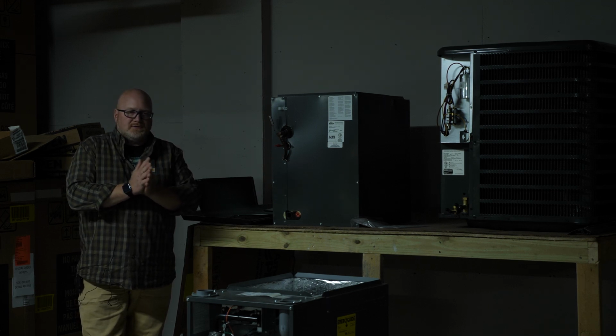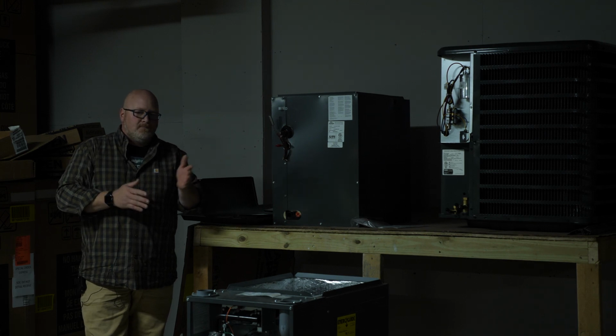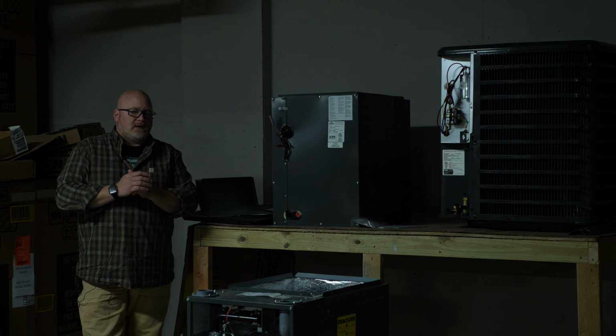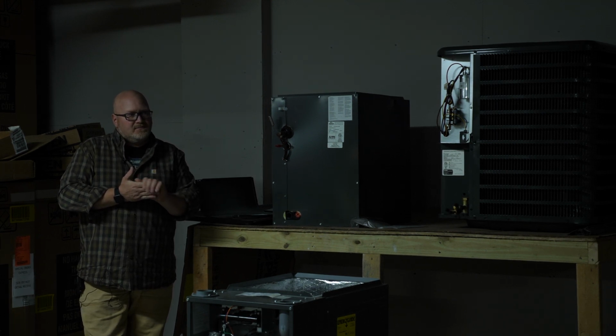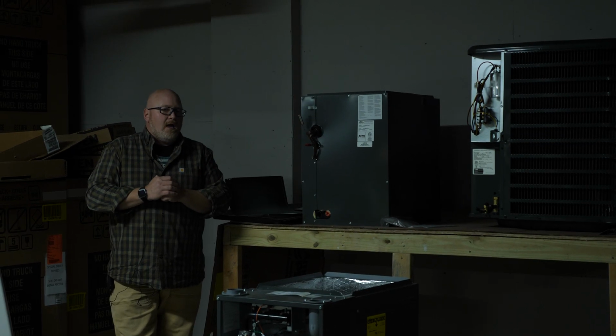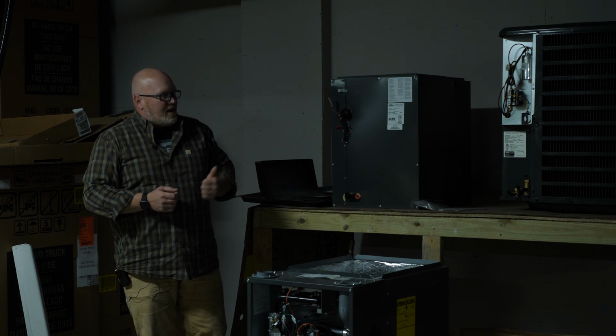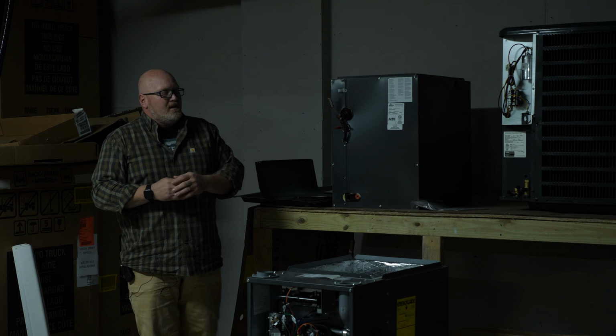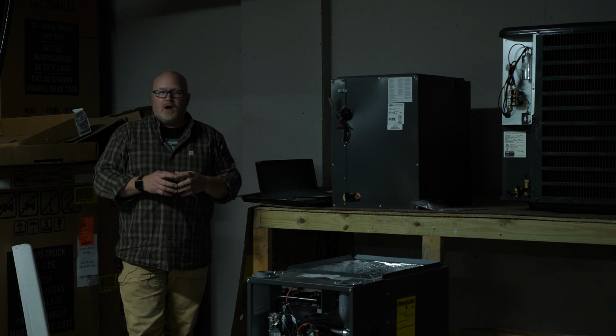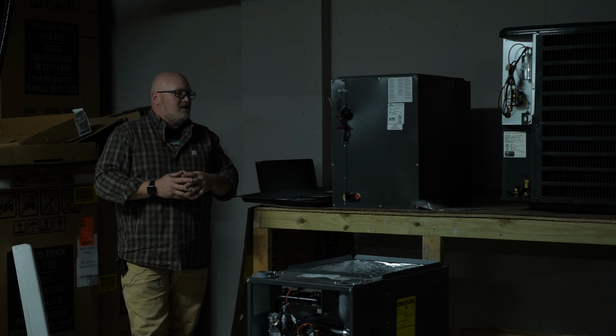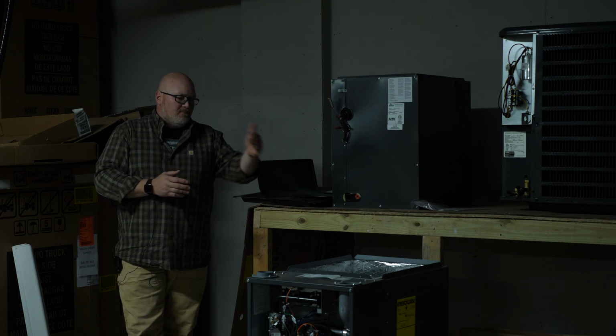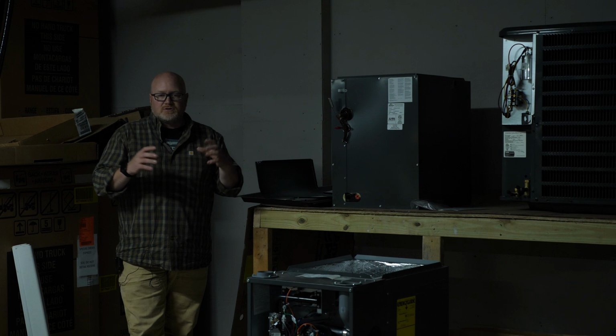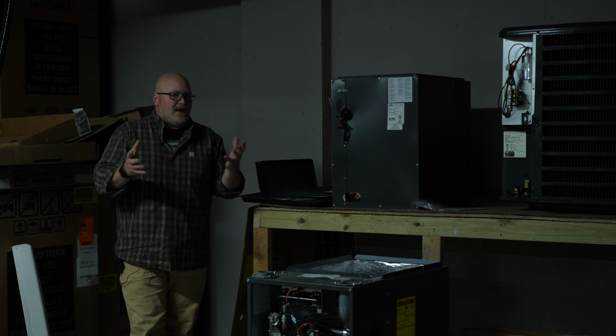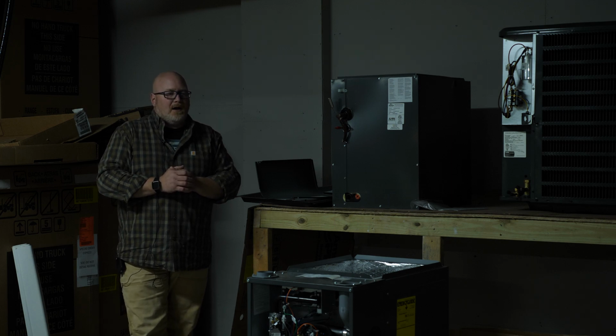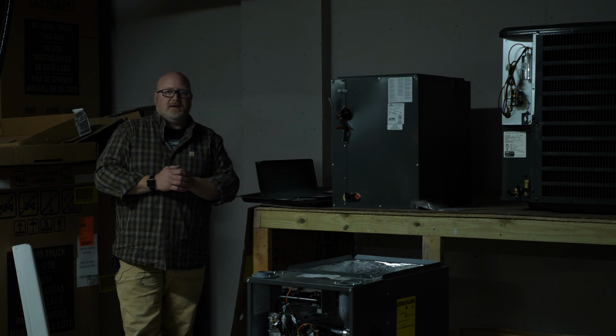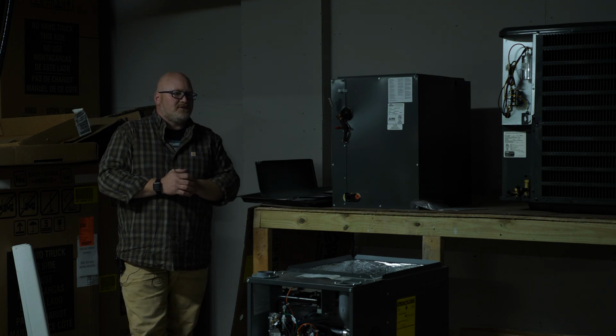In the last 20 years, in the changeover from R22 to 410A, during those first 10 years, I would say probably 80% of techs on the install got it wrong. The reason being is that R22, as a refrigerant in a system with a compressor and condenser designed for R22, is a hugely forgiving system. You can overcharge it, you can undercharge it, you can block air flow to a certain extent. The R22 systems were also running at a much lower pressure than 410A. Right now, probably about 90% of the market out there is 410A systems. There are a few R22 systems out there.